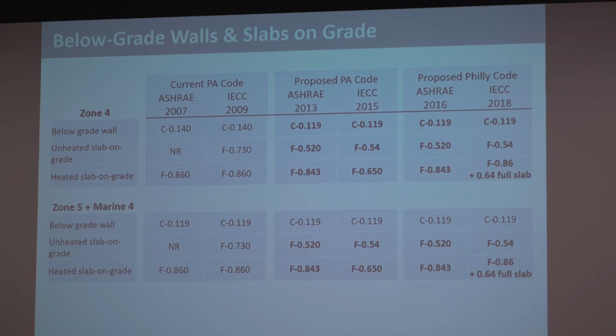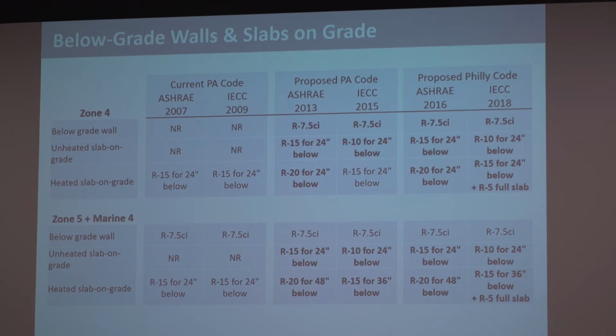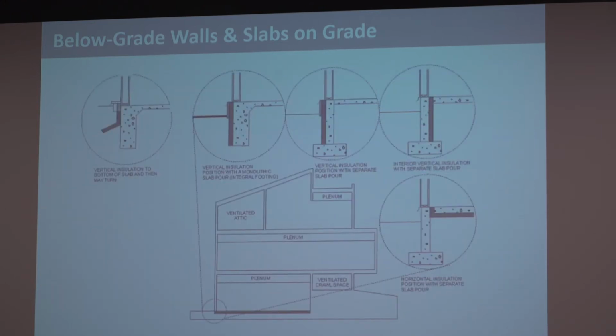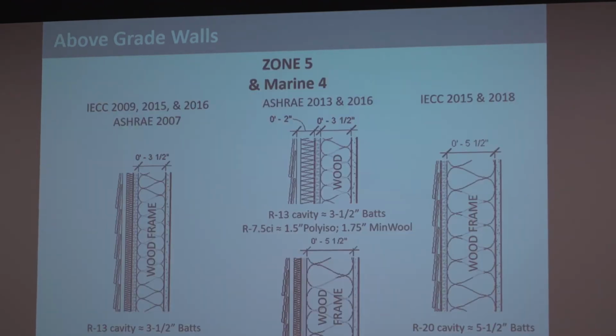There's tons of tables in ASHRAE to be able to look up. I've got a 12-inch foundation wall with 2 inches of insulation. What is my F factor? So there's pretty extensive tables to find out what those things are. Otherwise, you can just use a prescriptive version. It's pretty straightforward. Yep. Back on the above grade walls, the wood framing. Yep.